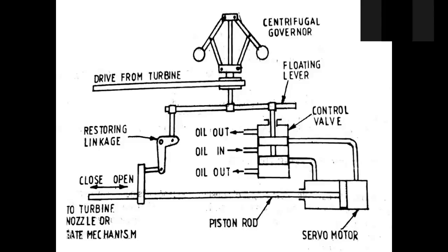When the nozzle is closed, the water which is hitting the turbine reduces, and hence the speed reduces. So what happens when electrical load reduces? When electrical load was reduced, the speed had increased. Now, because of the piston moving and closing the nozzle, the speed had reduced. Thereby, it controls the speed, and which in turn controls the frequency, which has to be constant.